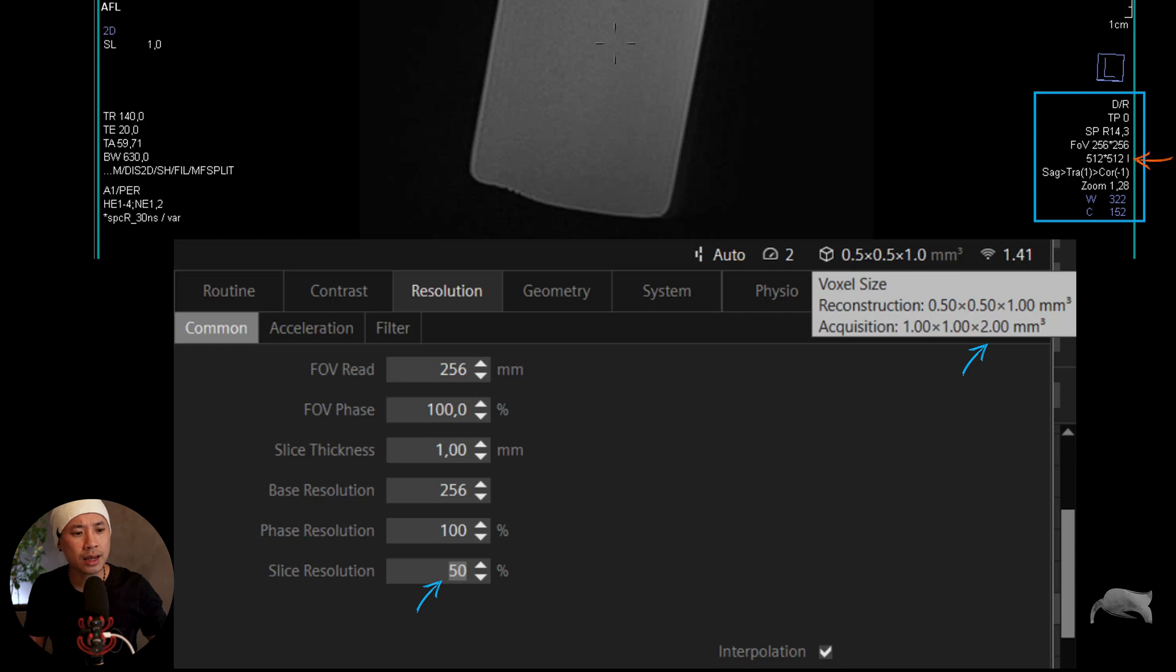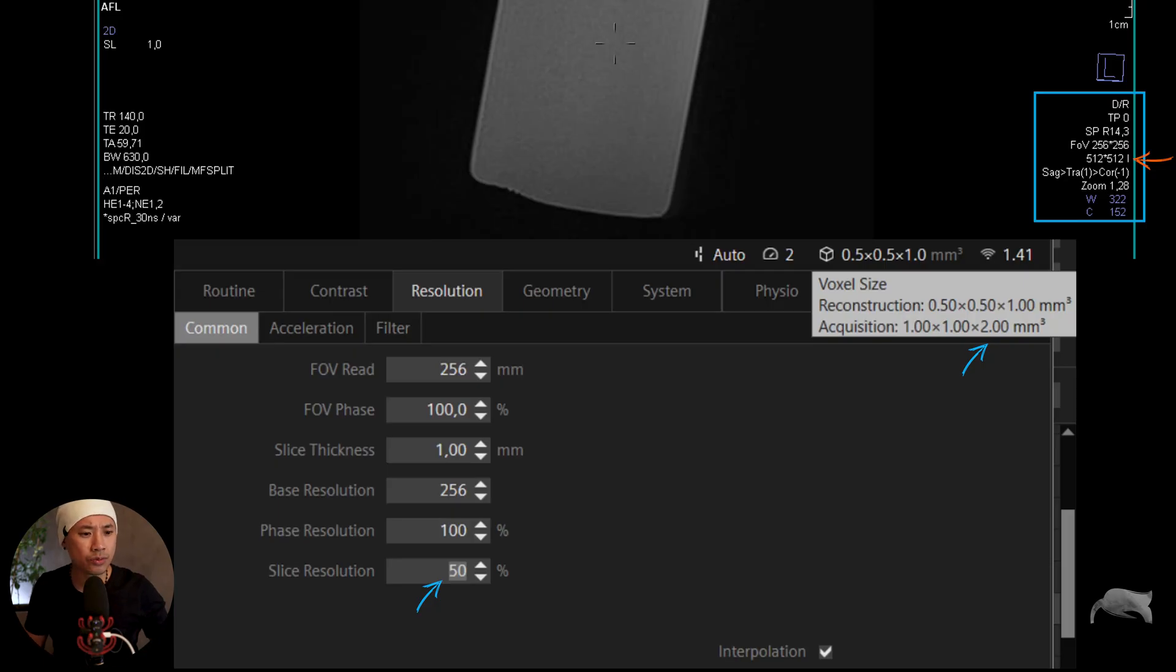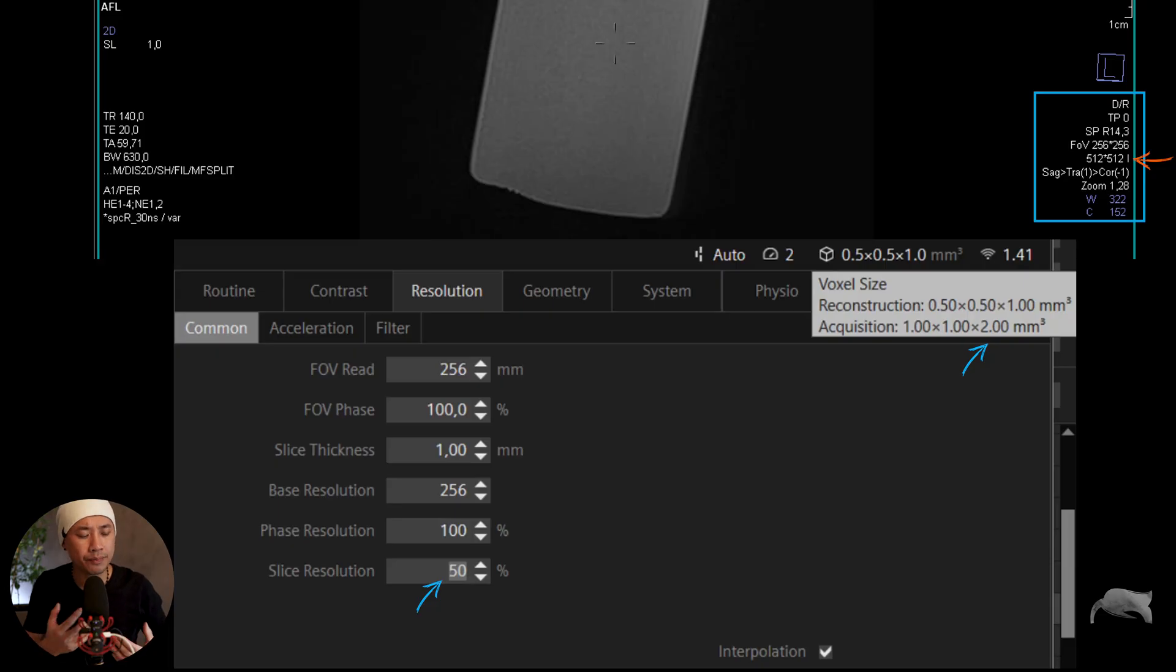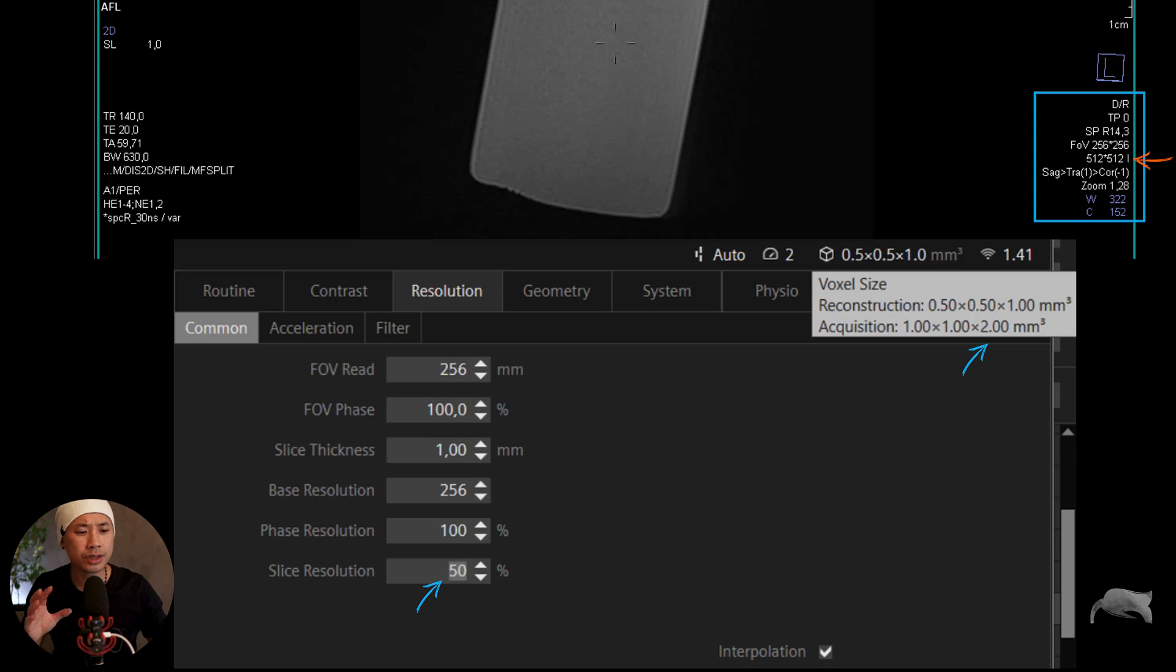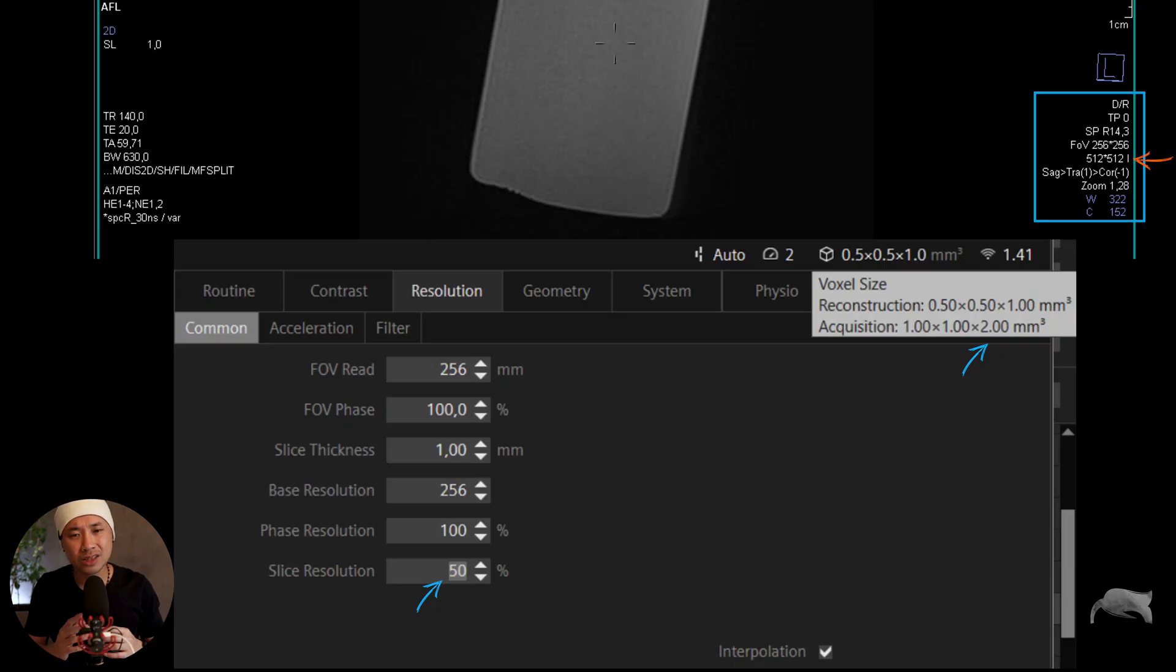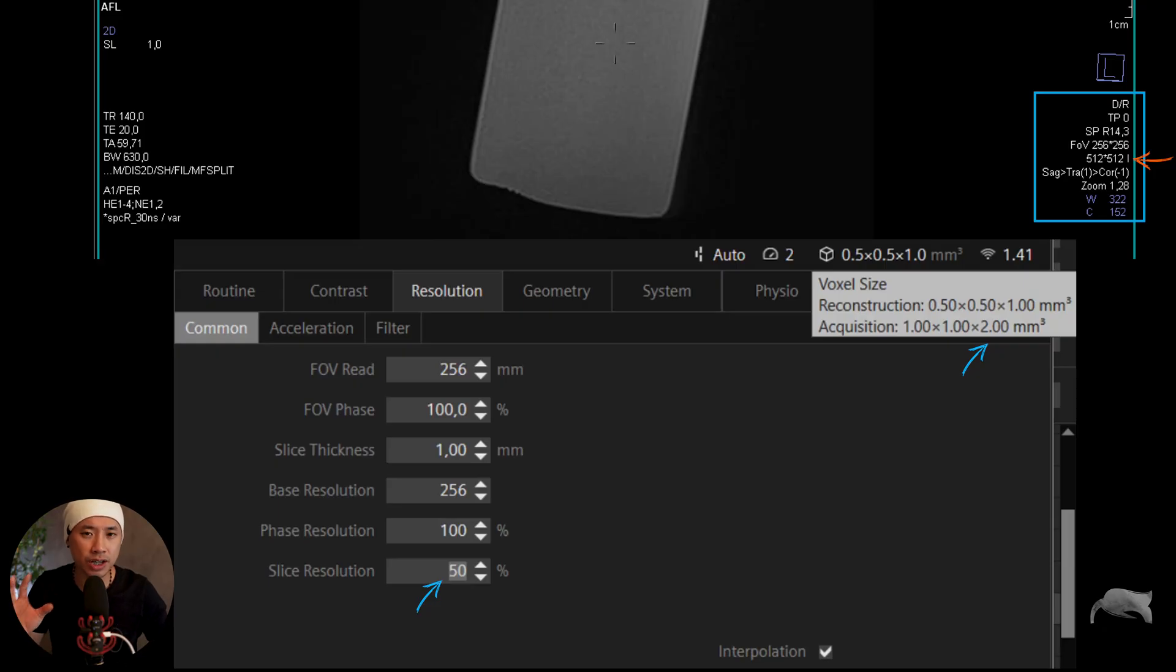But just note that the interpolation or the tag or the name here is just showing your frequency and your phase. It doesn't show you the slice. So that's very difficult because if I'm running the sequence, I only show you this - you do not know if I was using 50%, 60%, 70%, 80%, or 100%. You are only knowing if I'm using the interpolated on or off. That's what I'm trying to explain to you here by showing these images. So I really wish that there were some tags that could say 'I can see you're using 50%' because it does matter. Because it's now non-isotropic, you get of course more SNR and all that, but it's non-isotropic, there's blurriness on other planes whenever you're doing a reconstruction. So that kind of extra information is really good to know if you want to just look at the image annotation text, but it doesn't say so.